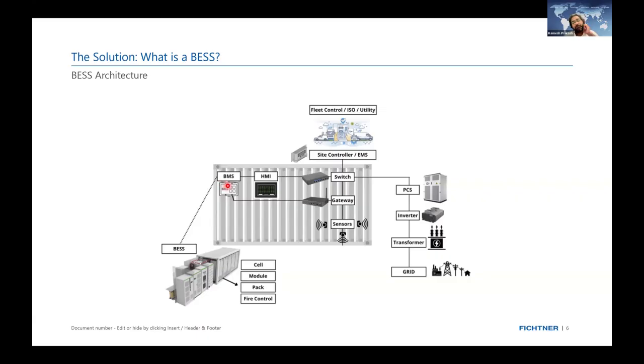For most devices or bikes, even e-bikes, the thermal runaway and thermal HVAC systems are not that efficient or maybe not present. So there's a possibility of fire, explosion, etc. But we cannot afford to lose a 5 megawatt hour 20-foot container to flames. So I need a proper HVAC and fire control system - a totally different control system working parallelly with my main system. There is no compromise in that.